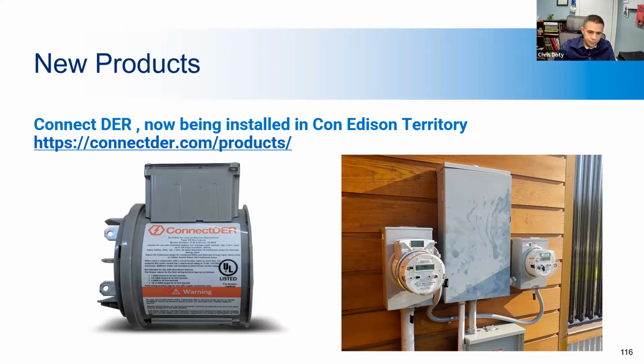And this requires that the connection be made in the meter pan. 2020 NEC will require that all meter pans, or it does require because it exists now, have a non-fused disconnect switch so that the meter can be serviced, and this could change where the connection point is for a lot of systems. And also this is handy because it allows the contractors installing your PV to stay outside your home, and they don't even have to come inside your home to install the whole system. So that's handy.